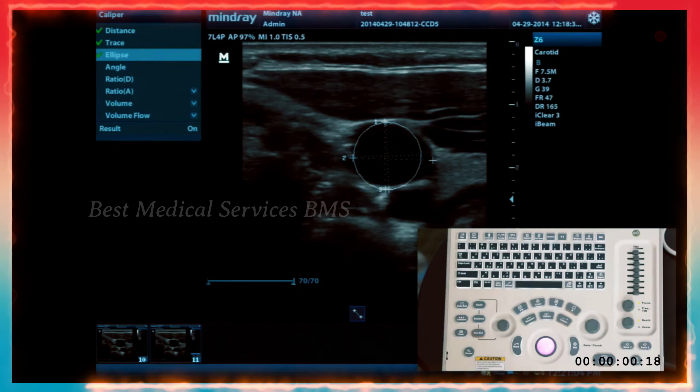You can see the body marker is yellow once locked in. If you want to pick it up and move it, use the cursor button to hover over it and hit the set button to re-engage its position on screen. If you want to change where the transducer is pointing, press set again and double-click with the set button in that area to re-engage where the transducer notch is.